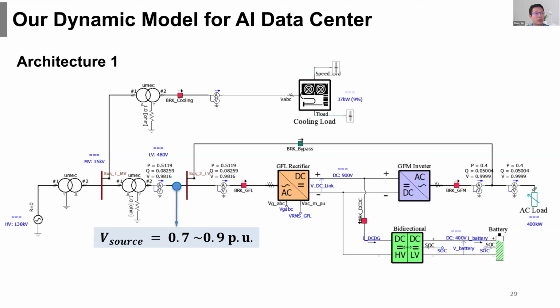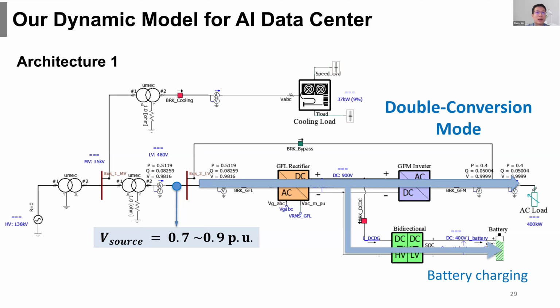But if the grid side voltage is getting worse, for example, if the grid side voltage dropped to 0.7 or 0.9 per unit, in this case, the power directly from the grid side is not qualified, does not have the high quality to connect with the AC load. In this case, the data center will switch to the double conversion mode. Double conversion means we will open this bypass switch and the power will go through the rectifier to convert AC to DC, then through this DC to AC inverter.